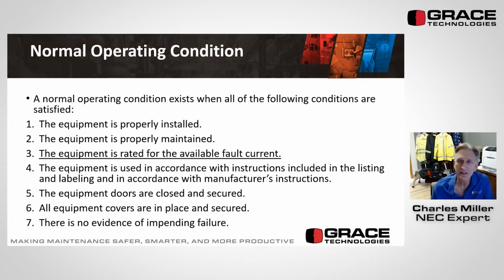Normal operating condition — this term came out several editions ago, and it was great when it did, because before we had normal operating condition, just to turn on a circuit breaker or disconnect switch, even if everything was closed up, we had to wear Category 0 clothing. Category 0 wasn't arc rated, but required a long sleeve shirt and long pants of a certain material weight. So if I were working in a plant or facility needing to turn off a breaker, even with the panel board door on and everything in great condition...